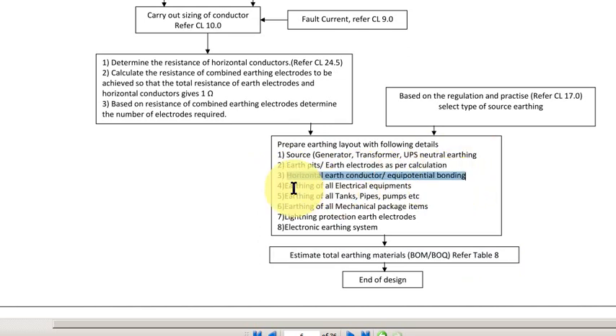And you have to show the earthing of all equipment - electrical equipment. You have to show earthing of all non-electrical equipment like tanks, pipes, pumps, etc. All mechanical package items like compressor skid, cranes - you have to show the earthing. And lightning protection system for buildings or pump house also has to be shown. The electronic earthing system for control room also has to be shown. That is about the layout.